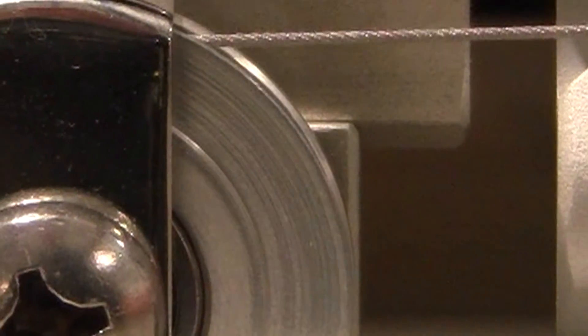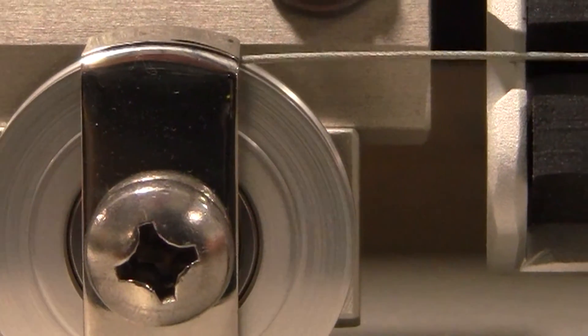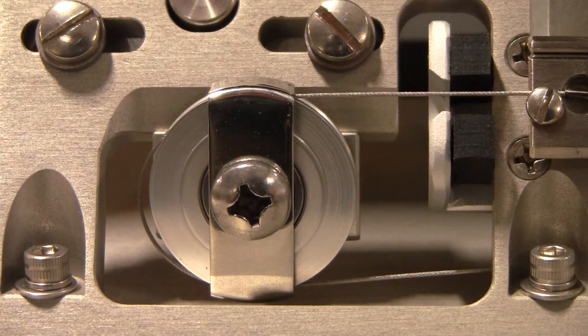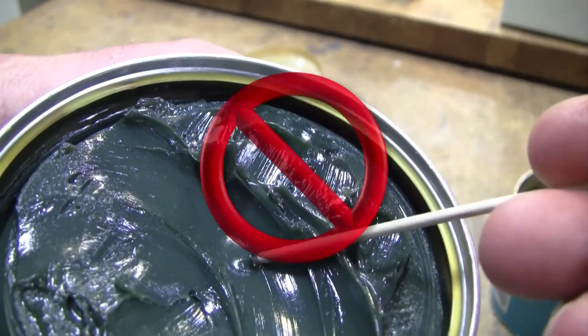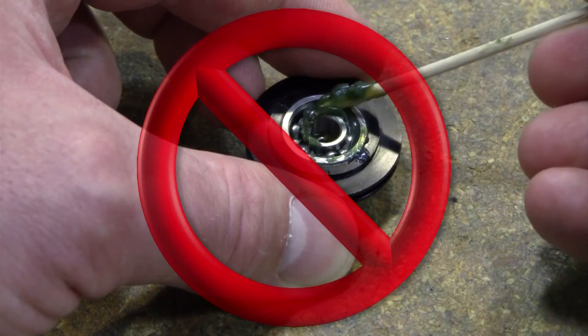Over time the small amount of lubricant that is contained in each pulley bearing will age and may eventually freeze up the bearing. Debris particles from the air will team up with the chemical aging of the lubricant to accelerate this process. Sometimes a well-meaning human being who applied some inappropriate lubricant to the bearings may have contributed to this.